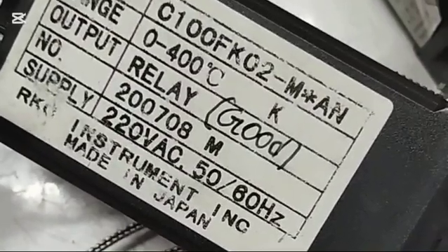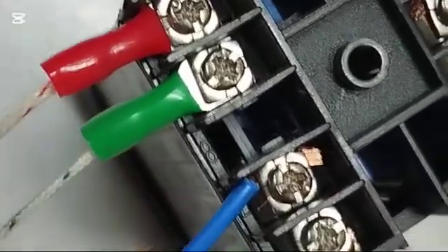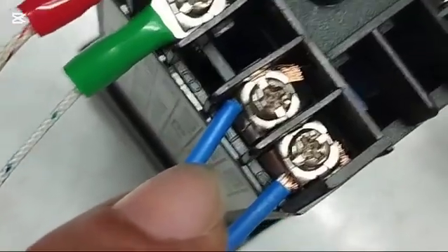This is relay type temperature controller. We connect temperature sensor thermocouple with 10 and 9. 10 positive, 9 negative. Alarm switch connection with 6, 7. Relay out 3, 4, 5. 3 is common, 5 and 3 NC, 3, 4 NO relay out.